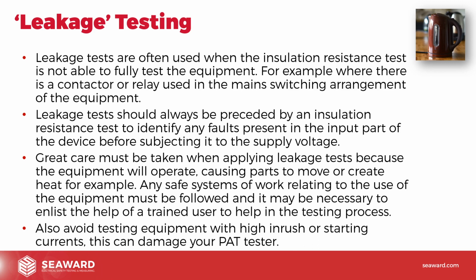Great care must be taken when applying leakage tests, because the equipment will operate, causing parts to move or create heat, for example. Any safe systems of work relating to the use of the equipment must be followed, and it may be necessary to enlist the help of a trained user to help in the testing process.